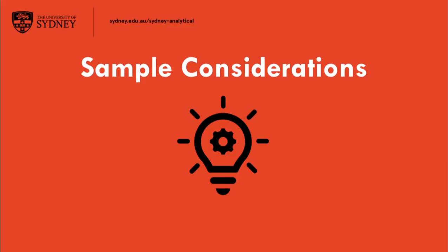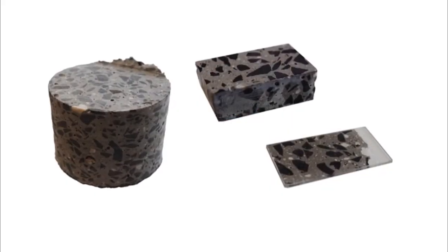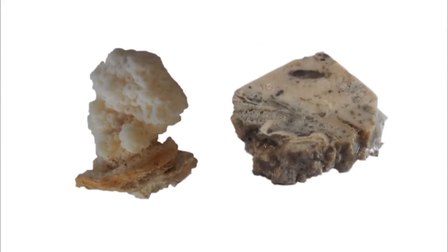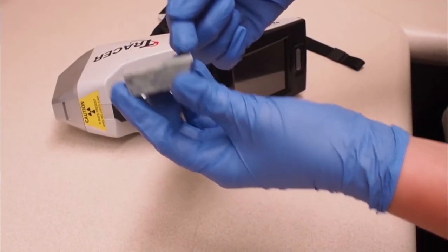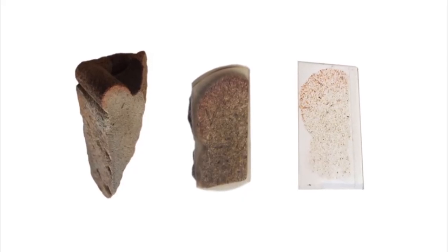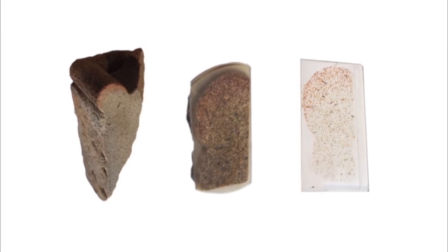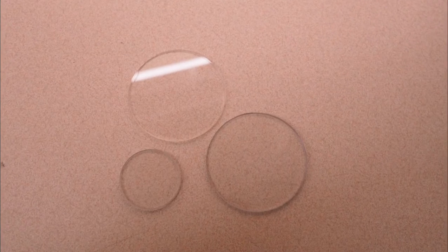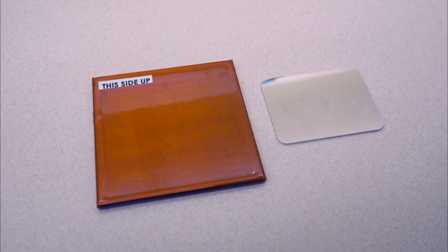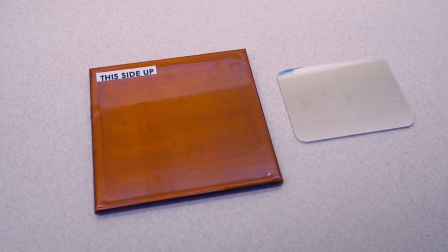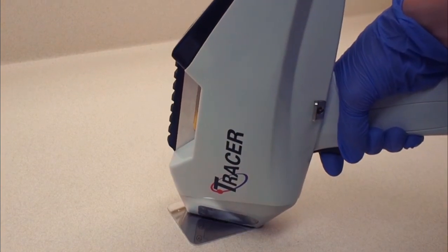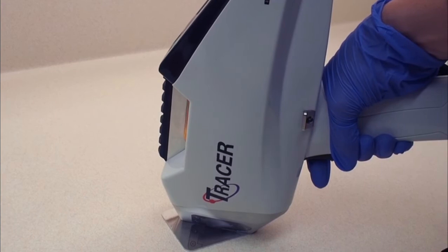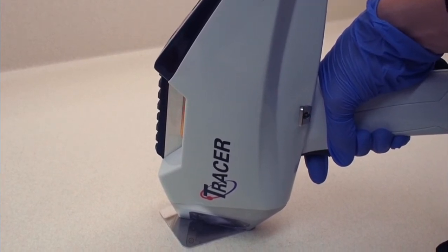Sample considerations. Preparation and mounting. Samples should preferably be flat and homogenous. Where this is not the case, we recommend that you analyze multiple spots with the flattest area possible presented to the instrument. Where samples are thin and being analyzed with a handheld setup, you should back the sample with a polycarbonate disc to eliminate spectral features from the otherwise underlying material or substrate, or the background metal plate, which will also absorb the x-rays. Your spectrum may still be contaminated with elements from the disc or plate, though these are relatively homogenous and potential spectral contaminants are well understood.